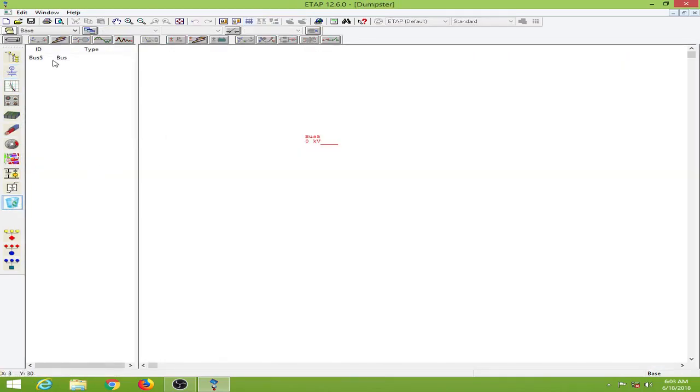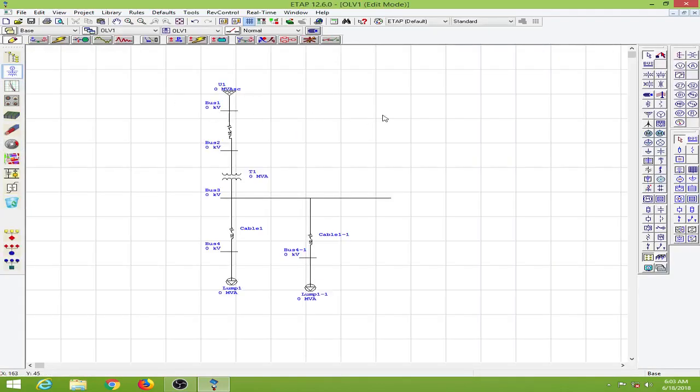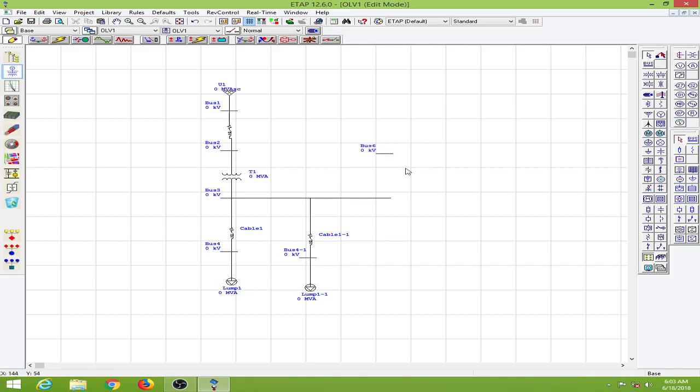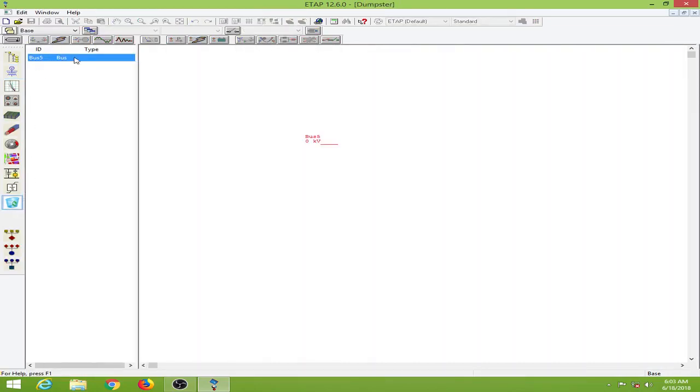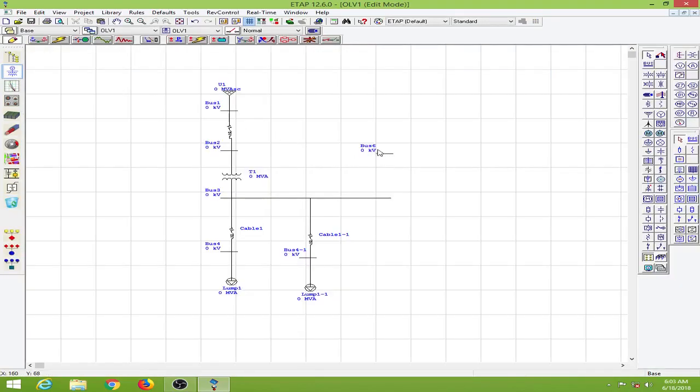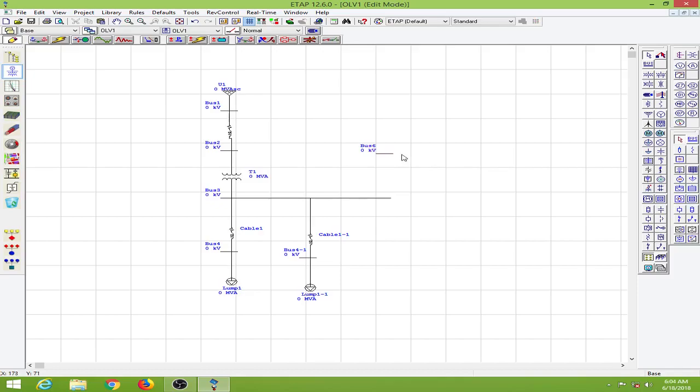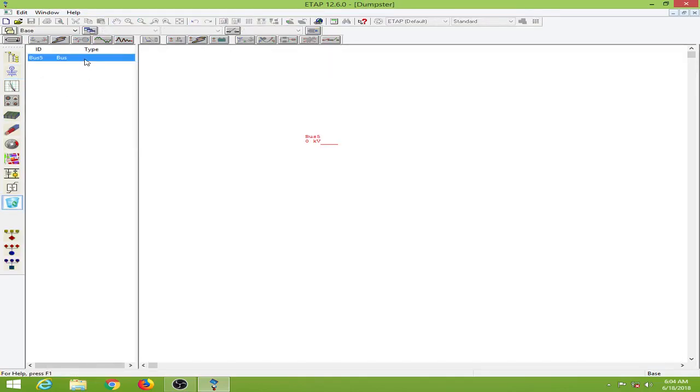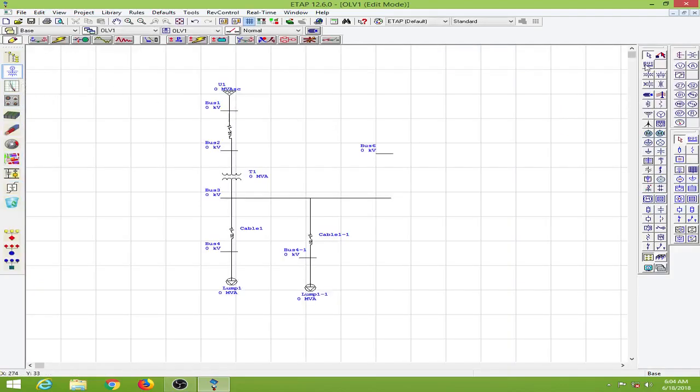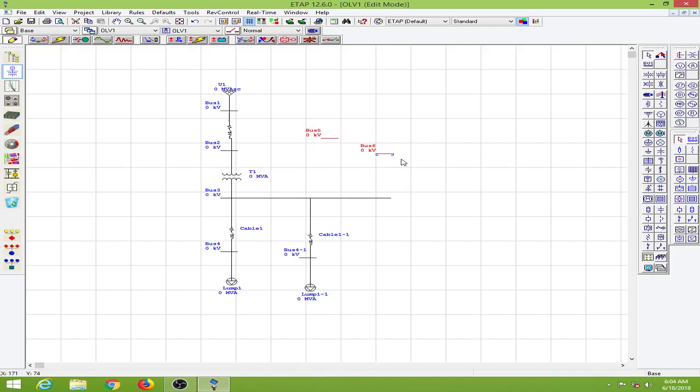If I want to bring back the elements to my single line diagram I could go back to the dumpster, copy this, go back to the single line diagram and paste it. Now the bus has come back. This is bus number 6. When I go back to the dumpster I can still see bus number 5. If you want to make this bus 5, you will have to go to the system dumpster and delete this bus. I will delete this and when I come back to my single line diagram and put over here, see this becomes bus number 5. And this is how it is done.